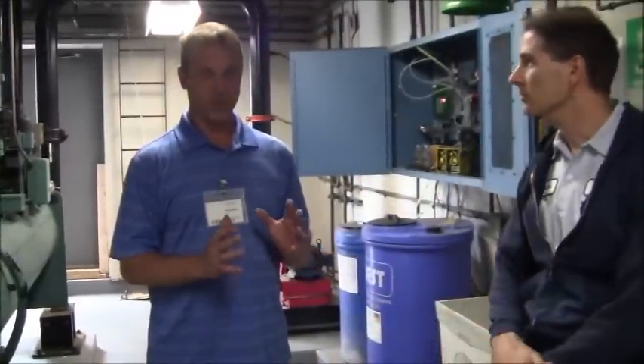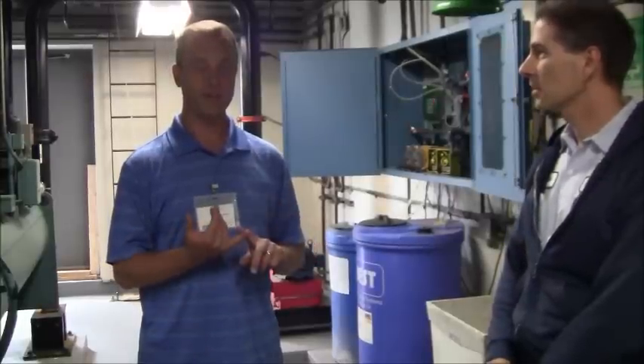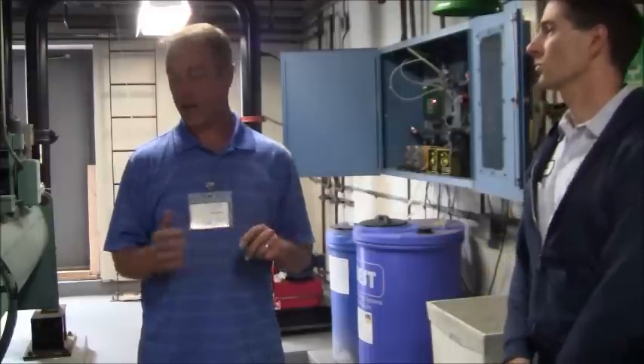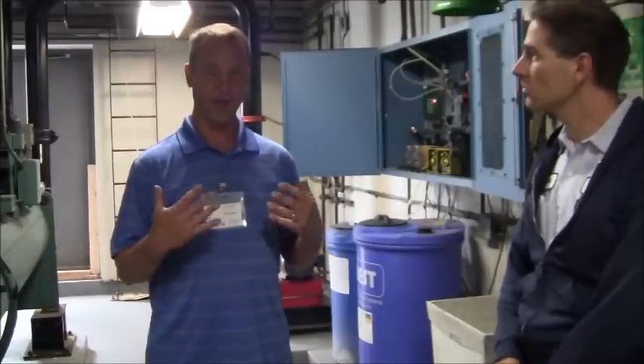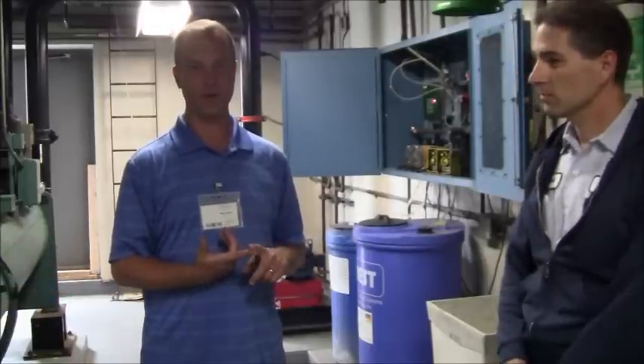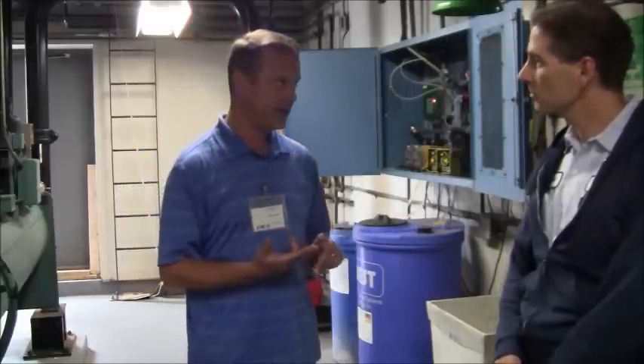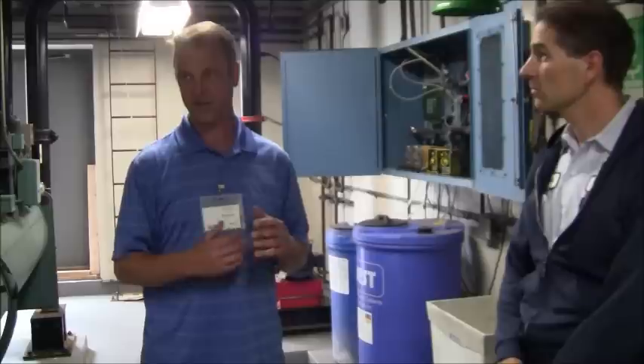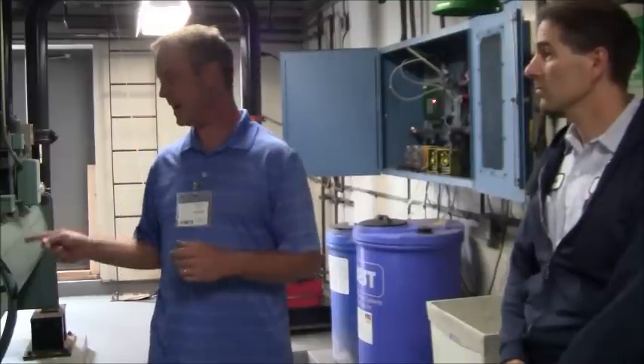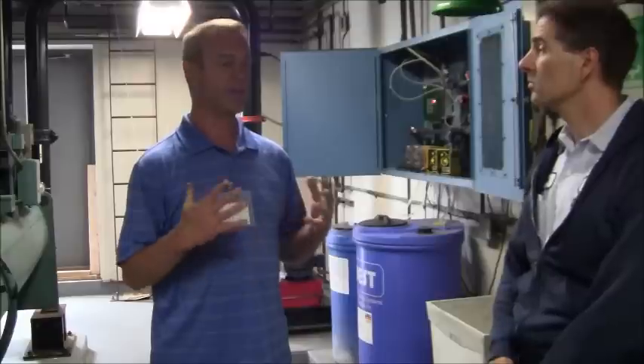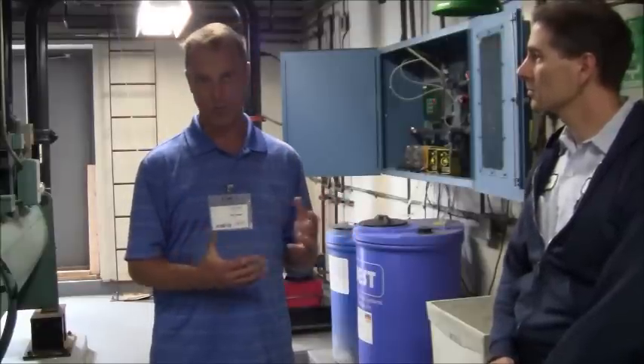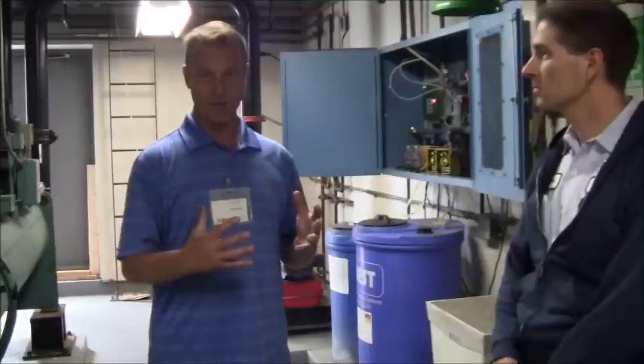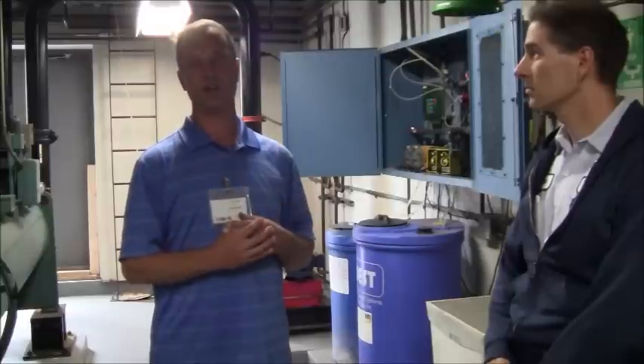The entire purpose of a water treatment program is to provide efficiency, water conservation, and maintain the equipment. So we're trying to be economical, but also maintain the building's assets. Water has plenty of impurities in it, like calcium and alkalinity. Everybody sees it on their shower heads at home or coffee pots, and you get scale. Well, that would be really bad if we get that inside the chiller barrel or cake up the fill in the cooling tower. Therefore, we start to lose energy and make the system work harder, raising energy costs. And these impurities can cause a lot of havoc.